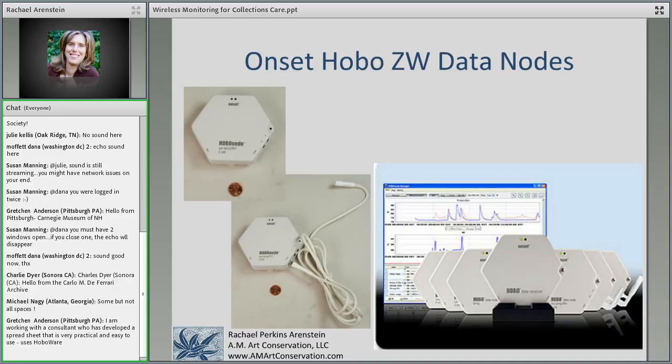When you read the wireless specs, they tend to talk about their transmission range. But it's important to note that for most of these systems, they're talking about line of sight, an unobstructed distance. So if they say transmission range is 100 meters line of sight, and you're setting that up in a place with walls, you've already cut down your transmission substantially.